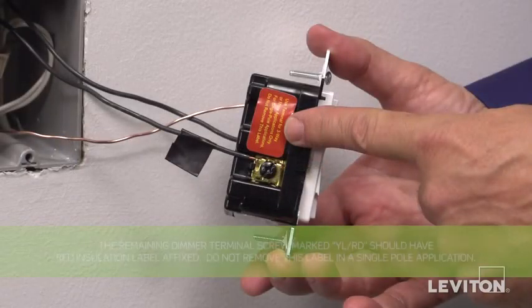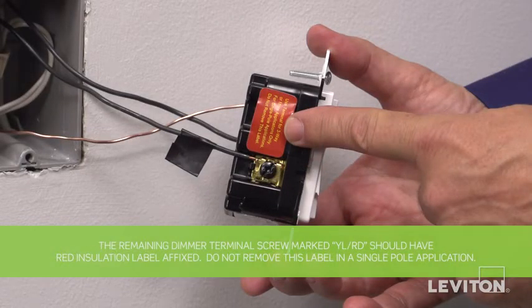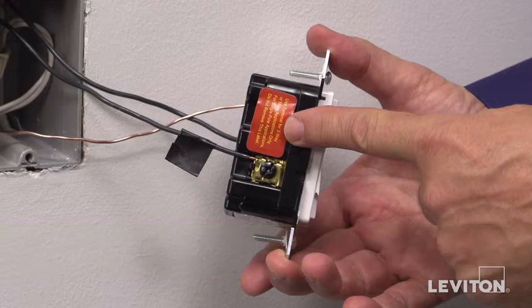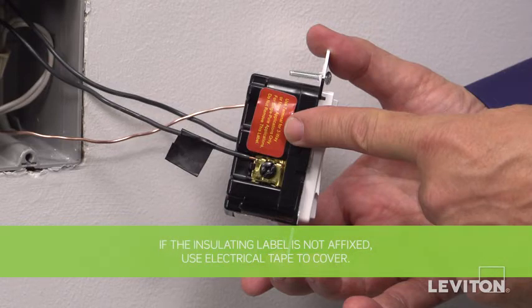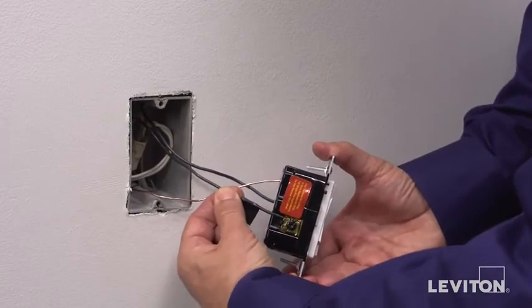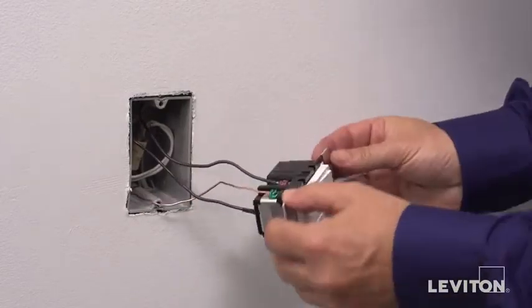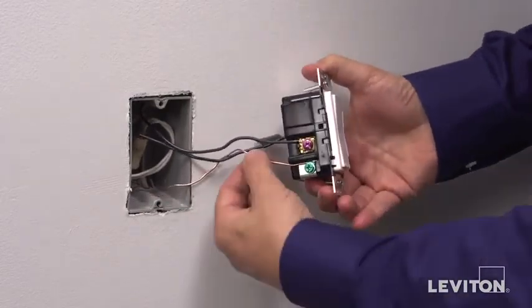The remaining dimmer terminal screw marked YLRD should have red insulation label affixed. Do not remove this label in the single pole application. Note, if insulating label is not affixed to yellow-red dimmer terminal screw, use electrical tape to cover. Tug on all conductors to ensure termination is secure. The device is now terminated.